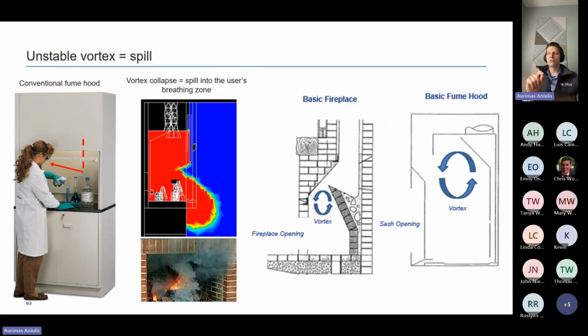The number one risk in the industry today is not some one big event in the fume hood, a big spill. It's micro spills in the breathing area of the fume hood users who use it every day. So in this example, this lady is mixing whatever chemical she's mixing on a regular basis. We're not worried about one big spill, because that can happen, just user error. But if the equipment's not properly balanced and she's getting a small microdose of this every day, there have been cases where people have sued the building owners for chronic illnesses, and the case went in their favor, meaning the building owners lost because they couldn't prove that their fume hoods were safe. No monitoring, no controls, nothing.